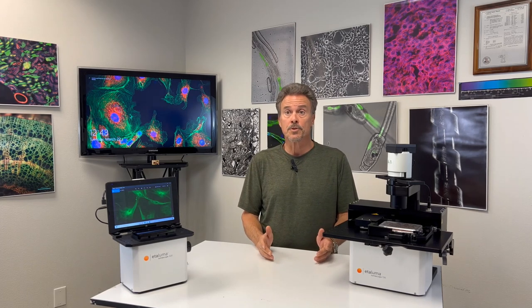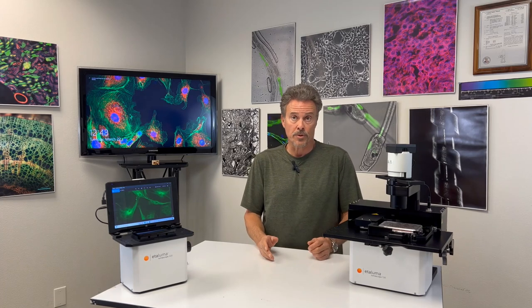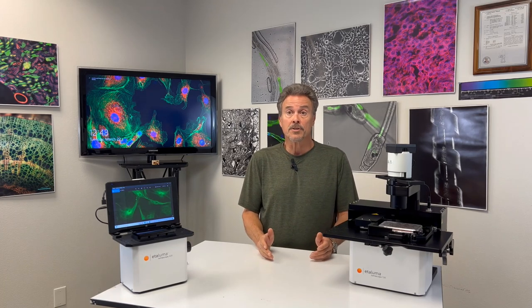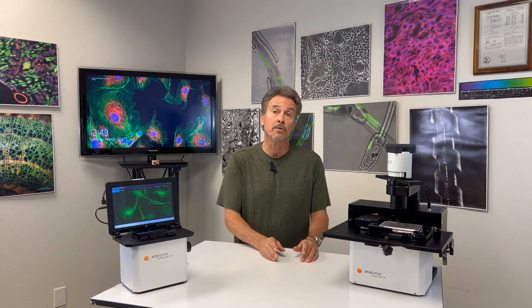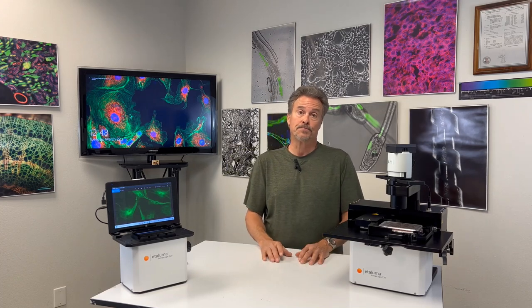Microscope precision and accuracy is another source of focus error. Higher magnification objectives require more exquisite focus due to their more narrow depth of field.